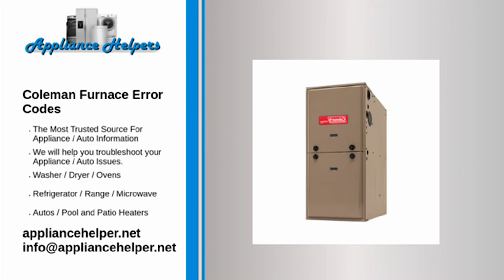Code: 3 red flashes. Problem: the pressure switch is stuck in the open position. Fix: check if there is a faulty inducer, a blocked vent pipe, a broken pressure switch hose, or a faulty pressure switch. Code: 4 red flashes. Problem: the limit switch is stuck while open. Fix: check for a dirty filter, an improperly sized duct system, an incorrect blower speed setting, or a faulty blower motor.